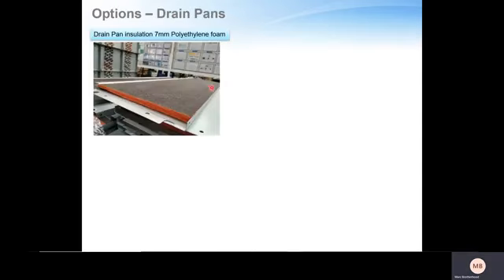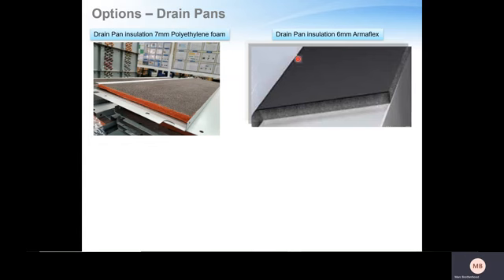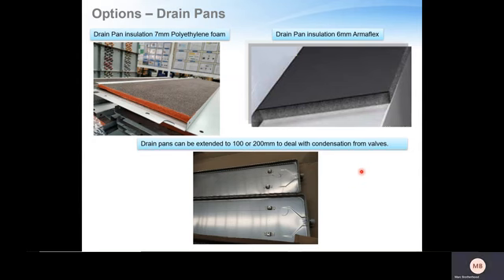On our drain pan options, it comes with the standard 7mm polyethylene foam, or the 6mm Armaflex option can be selected from the factory. Drain pans, we can also extend by 100 or 200 mils. These are always advised to have extended drain pans because your valves sit above these and your valves will always sweat. Valves could typically have an on-coil of around 6 degrees. The temperature in your ceiling void could be in the mid to high 20s, even peaking at 30 degrees, and it's going to create a lot of dripping condensate. So we always advise to go for the extended drain pans as an optional extra to prevent dripping in the ceiling and damaging ceiling boards or ceiling tiles.